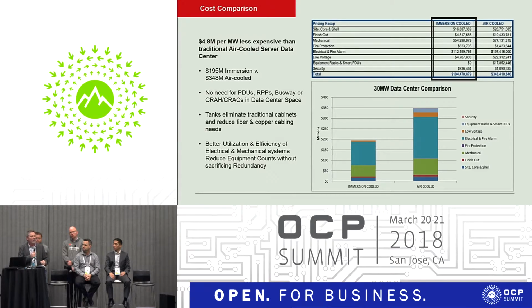Where we found the most savings in this was, of course, one of them is scale. But where we really found savings was in the amount of qualified, competent labor required to build this. Something we didn't talk about on the electrical infrastructure is the only two pieces of equipment here that are not off the shelf are your generators and your UPSs. The rest of this is pipe and wire, switchboards, breakers, controls that can be bought right off the shelf, right out of a catalog. Lead times are no longer an issue. Right, we go build a data center, we always worry about how fast can we get the equipment here. Moves us into schedule.